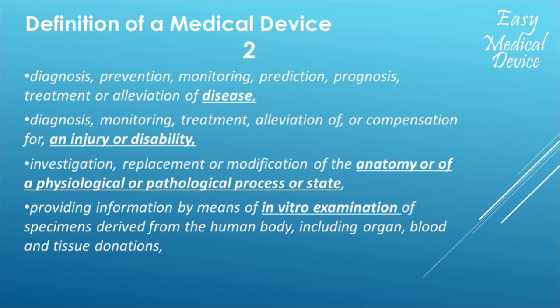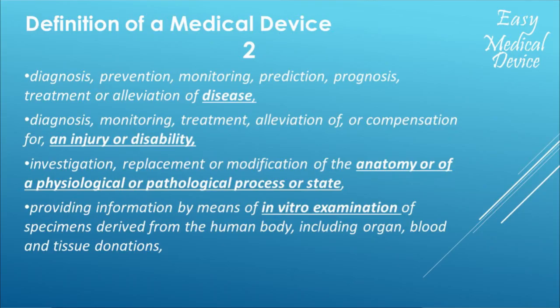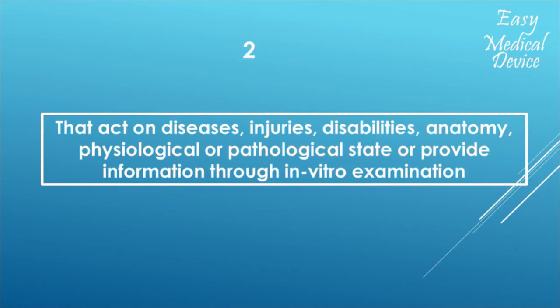Then: investigation, replacement or modification of the anatomy or of a physiological or pathological process or state. And the last one is providing information by means of in vitro examination of specimens derived from the human body, including organ, blood and tissue donation. How can I shrink this to one sentence? My proposal: something that acts on disease, injuries, disabilities, anatomy, physiological or pathological state, or provides information through in vitro examination.